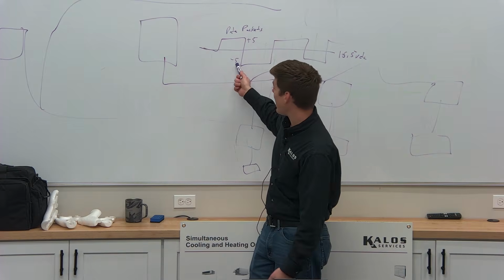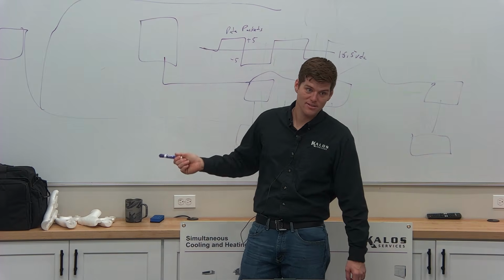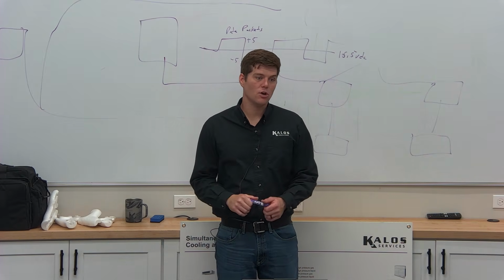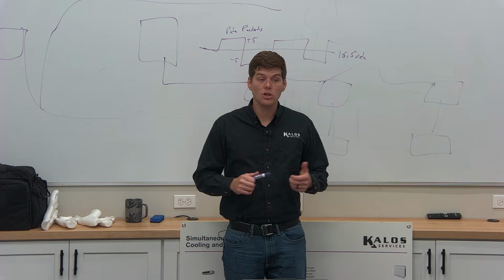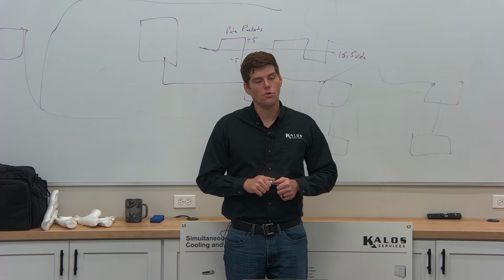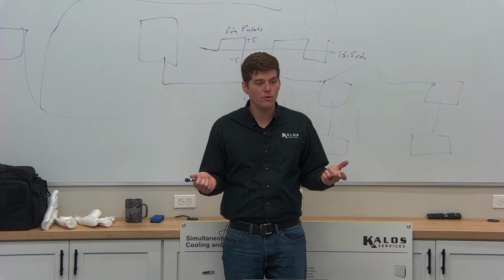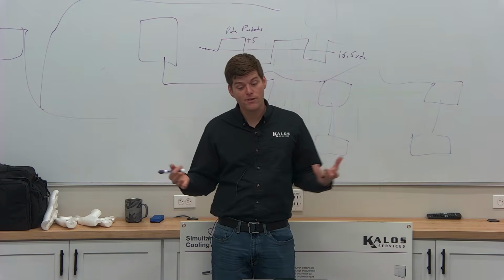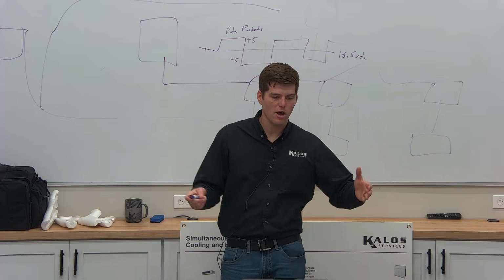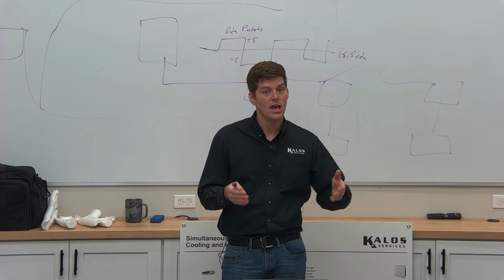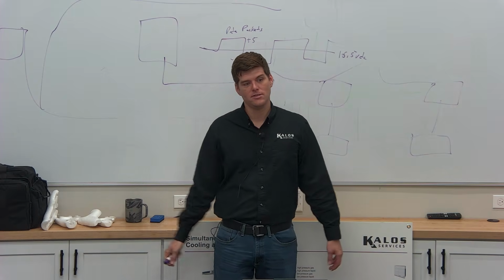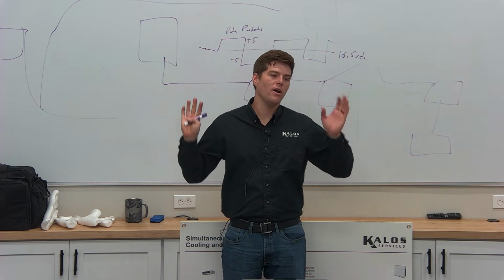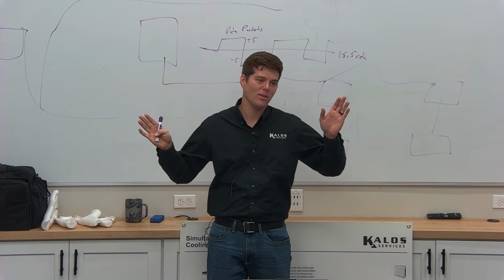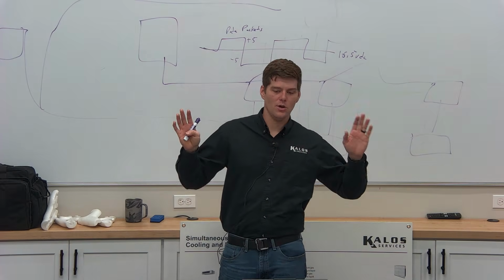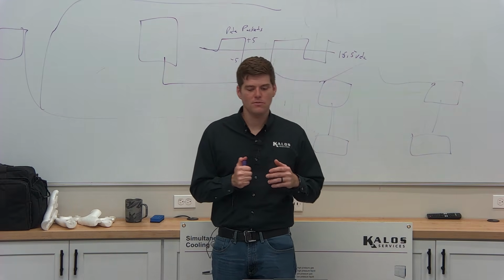We're talking data packets in milliseconds. They can easily get corroded, corrupted, changed, look like something else when you use solid core wire and run it close to a high voltage wire. The magnetic interference and frequencies and radiation that's given off from actual high voltage that you can't see actually interferes with stuff like this. Daikin says don't use shielded wire. They've had a lot of problems with shielded wire in the past and recommending it. Brian recently talked about it too, about using shielded wire.